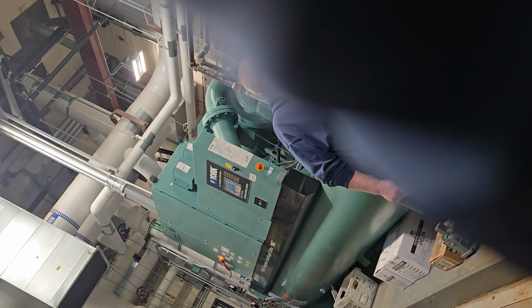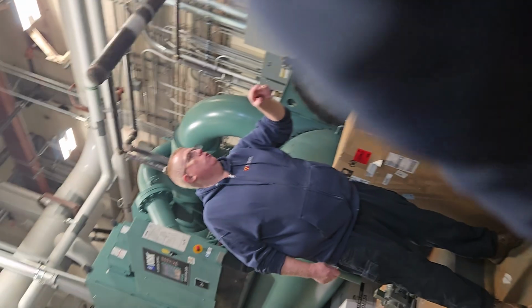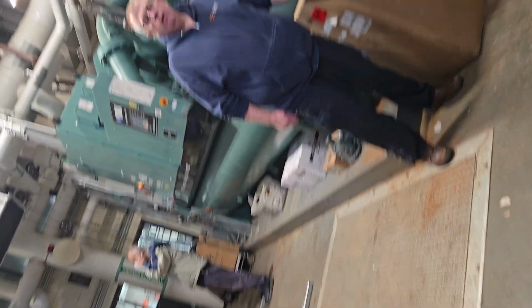What you have in this room are the chillers. This is where all the cooling is made for the main campus. We send chilled water through the tunnels all the way over to another building, and up to the top floors of the other building, where there are air handlers with chilled water coils. We send it to variable air volume systems, through ductwork, at around 62 degree air, depending on what the outside flow is, which determines what we run the cooling at. What you have behind me are two 600-ton units each, so there's 1,200 tons of capacity total.